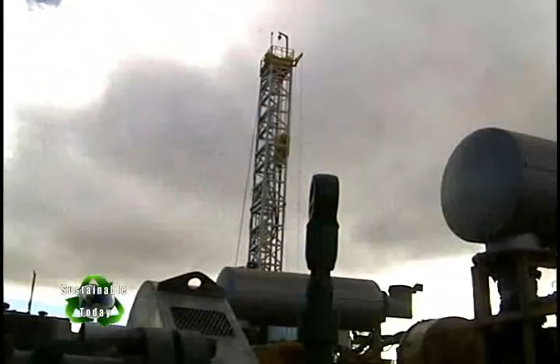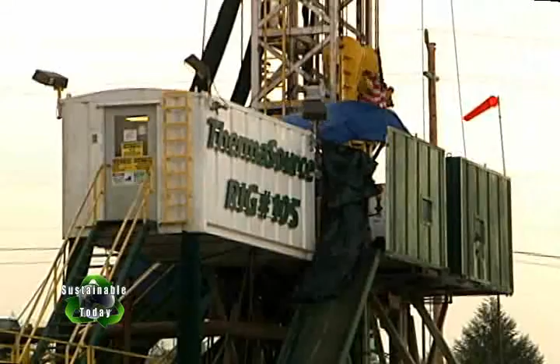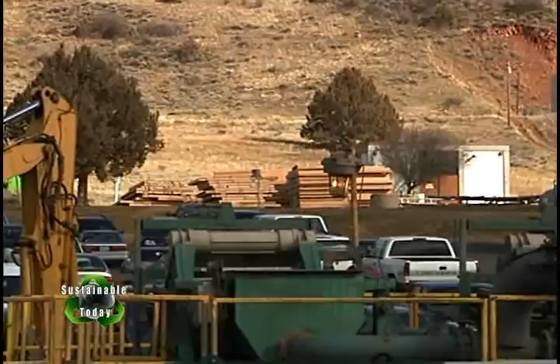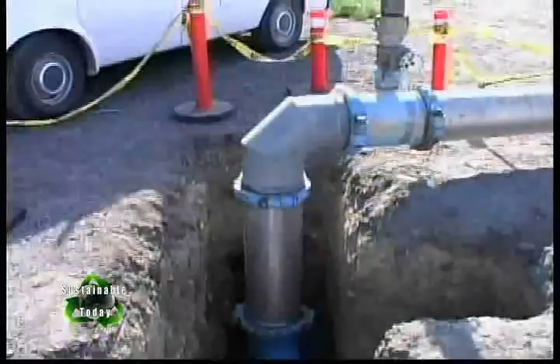In order to determine where we drill our wells, we did a seismic survey where we, on two different axes, drilled a series of holes and set off dynamite charges in each one of those holes. The sounding from that was recorded. We take those soundings, we look at where the fault lines are, and we locate our wells, both our production wells and our reinjection wells, based on that geology and the flow and direction of the groundwater resource.